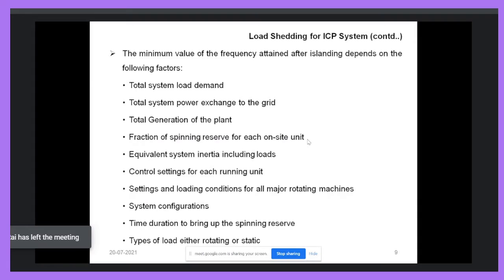Total system load demand: we know that the frequency variation depends on the load generation balance, so obviously the demand will affect the variation of frequency. Total system power exchange with the grid: before the islanding, how much power we are drawing from the grid also affects the frequency deviation after islanding. Total generation of the plant, obviously fraction of spinning reserve. Spinning reserve means the power which is reserved for sudden changes in load and generation or any operating condition. So the frequency deviation depends on that also.